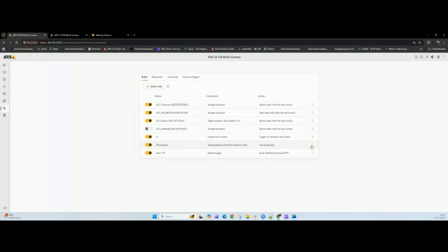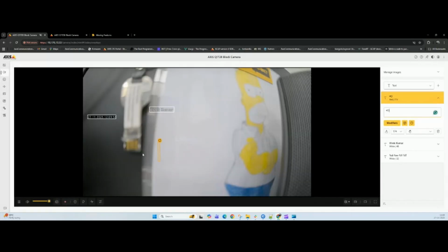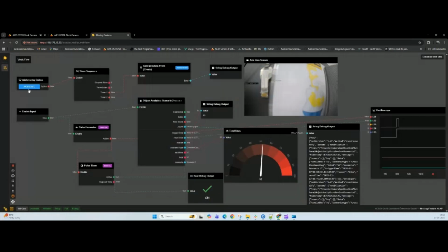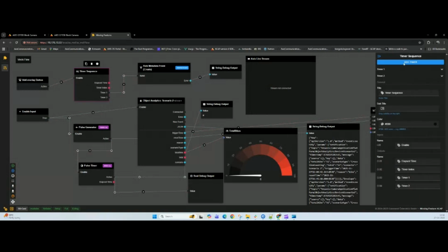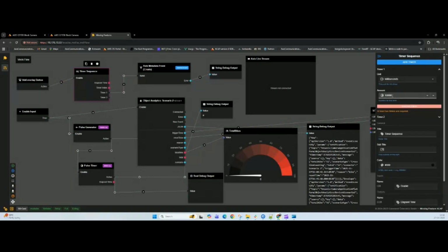And then there's the flip-flop node, the classic latch that holds a state until it's reset. And the documentation makes a big deal about the choice between RS and SR modes. Reset dominant versus set dominant. Why does that matter in practice? It matters for safety and for priority. In RS, or reset dominant mode, if both the set and reset signals arrive at the exact same instant, reset wins. Reset always wins. This is critical if your reset input is tied to, say, a safety shutdown. You always want the shutdown to override a simultaneous command to start something. So it gives the logic a clear hierarchy. For safety, you pick RS mode.